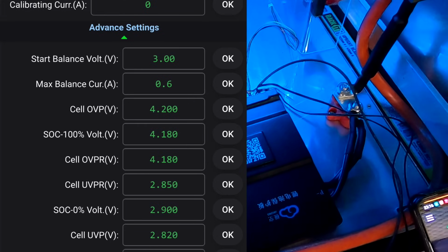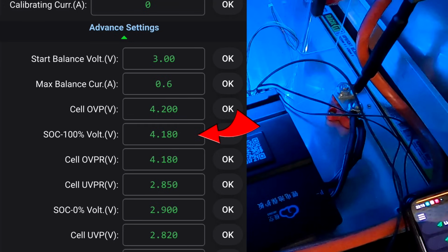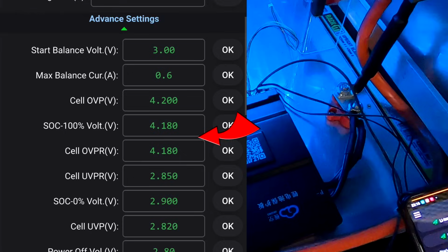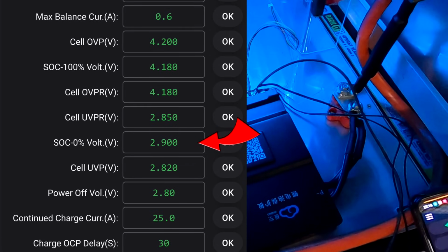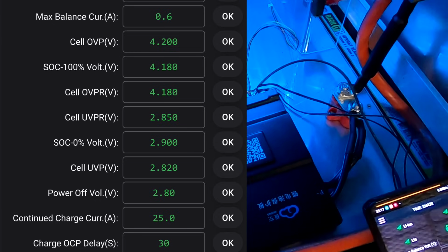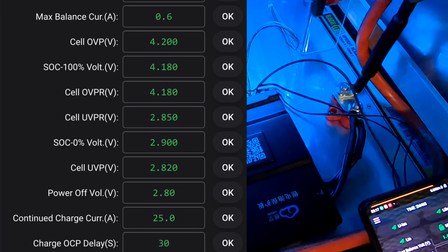And we can also see that we have a so-called 100% voltage. So we can actually set a reset voltage here in the BMS for when it goes back to 100%, so you don't need to hit the over voltage protection anymore. You just need to hit this voltage here to reset to 100%. And the same for the 0% - you can set a low voltage where it shows 0%.